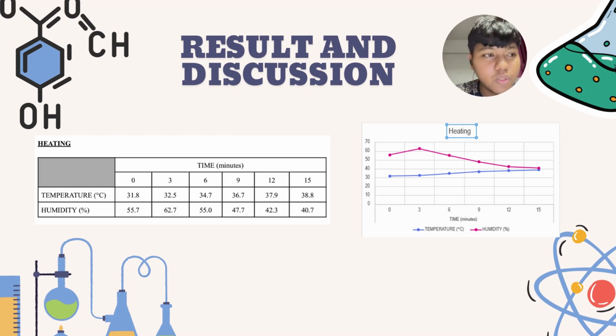So although no moisture is being removed, heating the air increases the moisture holding capacity, resulting in the relative humidity decreasing even if the actual moisture content remains nearly constant. So in conclusion, heating raises the air temperature and generally lowers the relative humidity due to increased air capacity to hold water vapor.